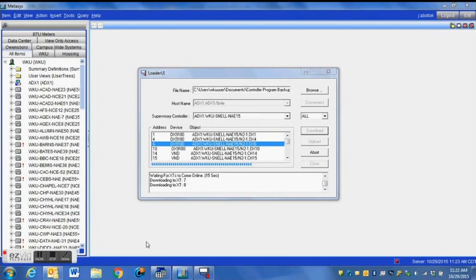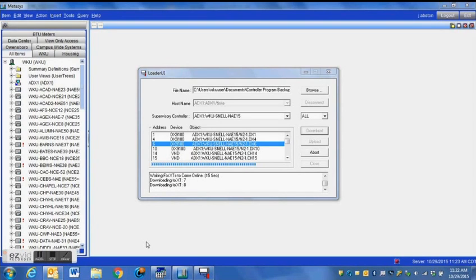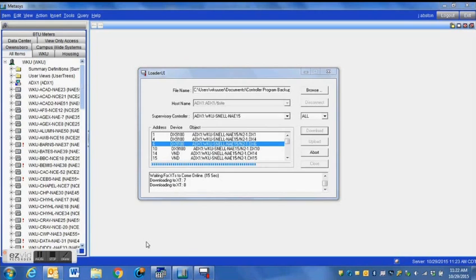Something that I wanted to note on this is for a brief period of time, all of your outputs on your controller are going to remain in their last state. If you have a motor running, it should continue running, although there's no guarantee of that. I highly recommend that you shut the system completely down before you actually do the download. That way you'll protect your equipment.